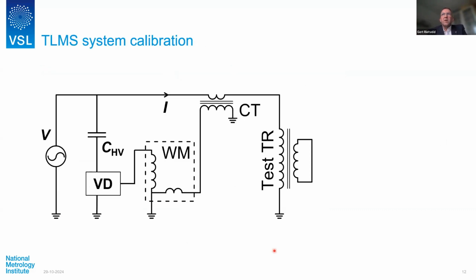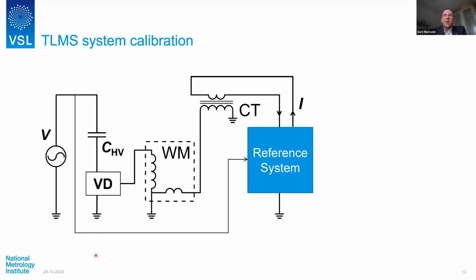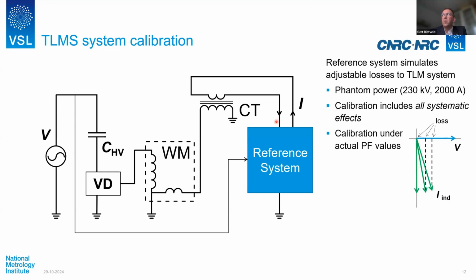And how are we doing such a system calibration? What is the approach? In order to make that clear, I again draw the picture of the typical loss measurement of a power transformer. What we are doing in the calibration is the following. We are replacing the power transformer by our loss measurement system, or reference system. We measure the applied voltage and then generate a current. Again, phantom power, like Ilya explained, we generate a phantom current to the current transformer with a phase that can be adjusted. So we can apply exactly 90 degrees, no losses. We can adjust the phase so that we can have any losses and calibrate the loss measurement system under any losses that are relevant for the particular power transformer manufacturer.